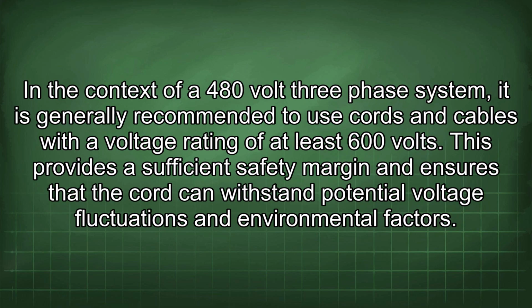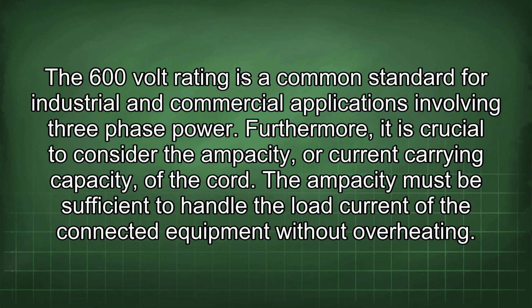In the context of a 480-volt three-phase system, it is generally recommended to use cords and cables with a voltage rating of at least 600 volts. This provides a sufficient safety margin and ensures that the cord can withstand potential voltage fluctuations and environmental factors. The 600-volt rating is a common standard for industrial and commercial applications involving three-phase power.